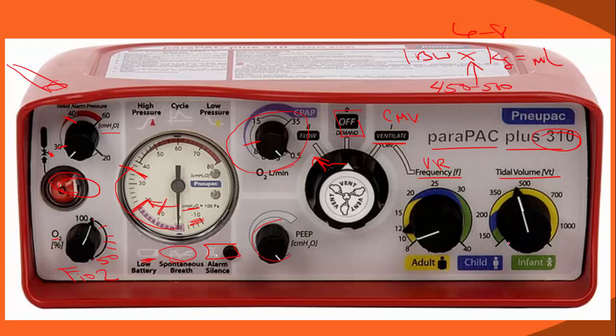So we notice that the colors here on the settings indicate patient size, so it's a little bit more paramedic proof than we would think. So our range for the adult, 8 breaths to about 20 breaths, so that we can set which breath rate we want there. Smart medicine, we would determine what's wrong with our patient. Maybe they need to breathe a little bit faster to blow off that CO2. Maybe they need to retain some CO2 given our patient's condition. The blue area is going to be for children, and then green for infant.